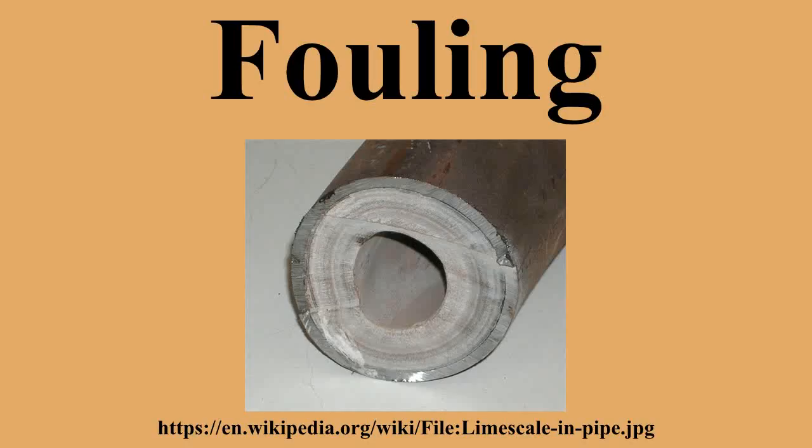transfer coefficient with time. If under-deposit crevice corrosion is of primary concern, it is important to note non-uniformity of deposit thickness, localized fouling, packing of confined regions with deposits, creation of occlusions, crevices, deposit tubercles, or sludge piles. Such deposit structures can create an environment for under-deposit corrosion of the substrate material, e.g., intergranular attack, pitting, stress corrosion cracking, or localized wastage. Porosity and permeability of the deposits will likely influence the probability of under-deposit corrosion.